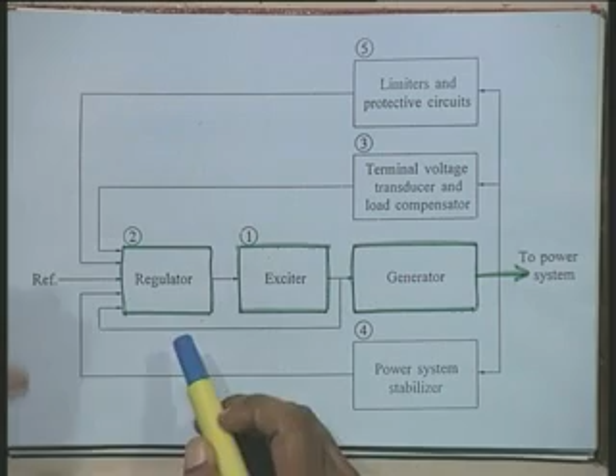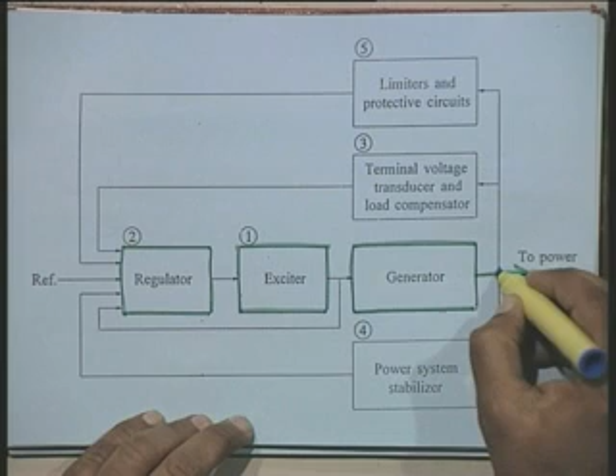As I have told you, the primary function of the excitation system is to provide DC current to the field winding of the synchronous generator, okay. And we provide various controls and protection systems, so that we achieve the requirements of the system from the generator considerations and from power system considerations. Now, first let us look at how we maintain the terminal voltage. How do we do it? We sense the terminal voltage from the synchronous generator terminals. Okay.